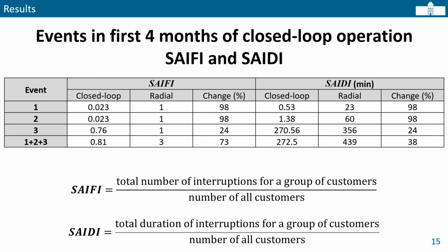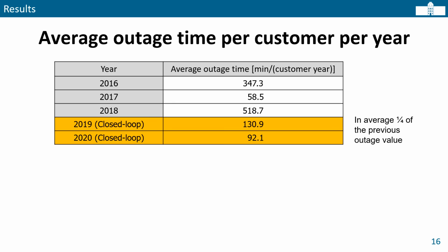When it comes to power supply reliability, indices SAIDI and SAIFI, for these three events, these indices were improved substantially. Perhaps what is more important for the network users is the average outage time per customer per year. And in this case, you can see that the average outage time after the introduction of closed loop operation was just 1/4 of the previous value of the outage time.